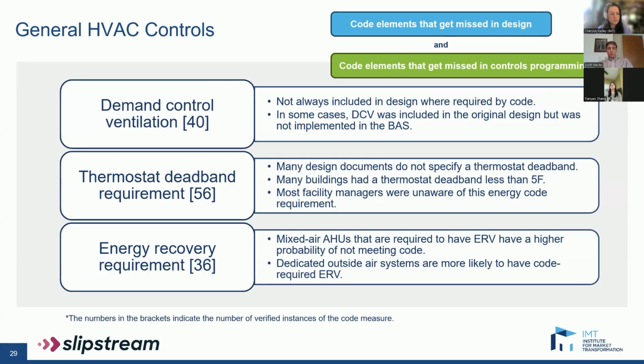Many of the facility managers that we talked to were unaware of this code requirement. And in many cases, the design documents did not specify a thermostat deadband at all, signaling that the designers may not realize this is something that needs to be called out in the drawings. And in a few cases, this was documented as code compliant in the original design, but the design sequence was not carried out in the BAS, or it was changed by building operators shortly after occupancy.